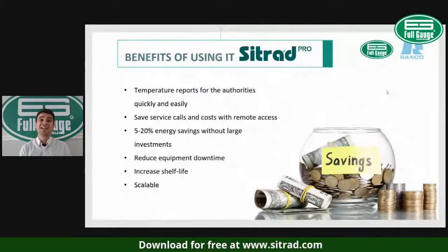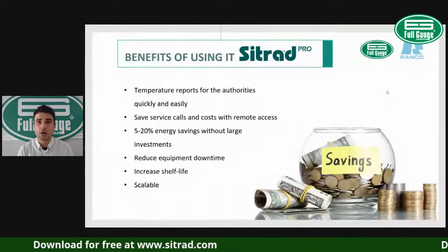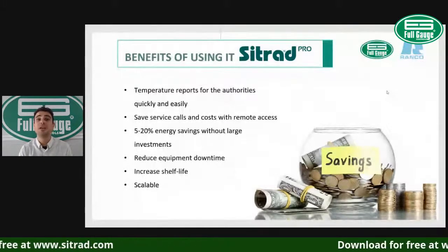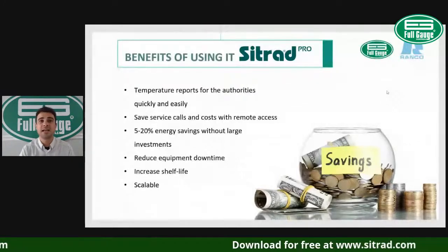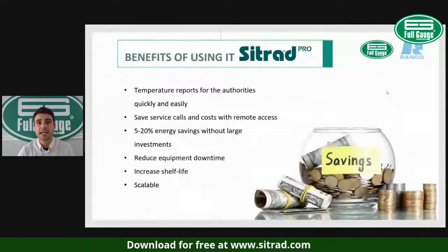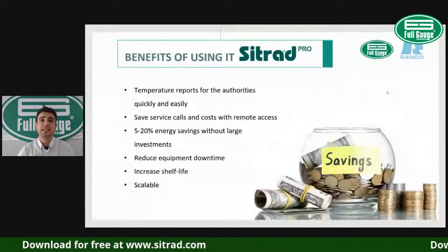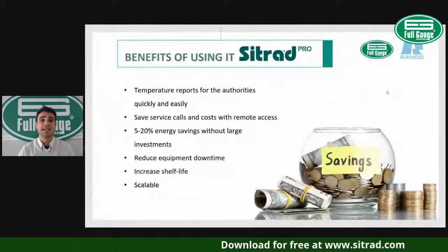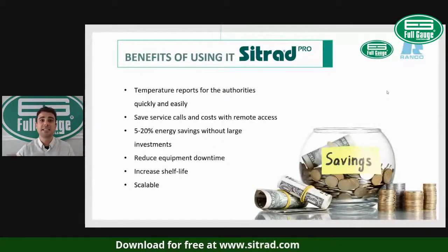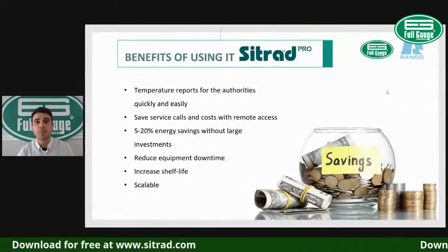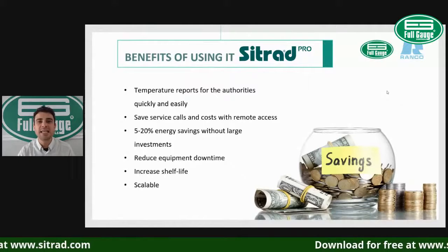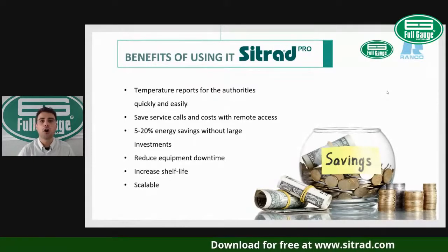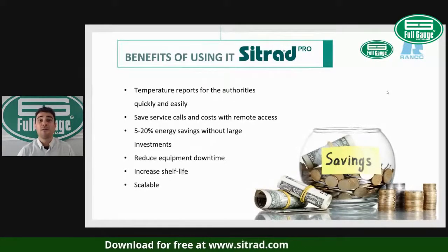Well, if you had Sitrad installed at that site, you could easily prevent that unnecessary travel to the site, because first of all, Sitrad would send you an open door alarm. In addition to that, you could take the temperature chart report and easily identify that your coil was blocked with ice.